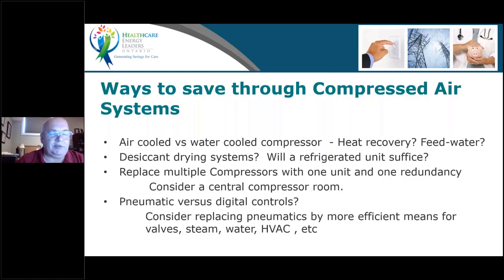Multiple compressors, so many plants have smaller multiple compressors located throughout the facility. Will one compressor do the work? Consider possibly a central compressor room. At the same time, consider a central compressor controller that will manage all the compressors simultaneously rather than having a pressure cascade where we set 3 or 4 compressors all at different pressure settings in case one fails and so on and so forth. That pressure cascade is a large waste of energy because we have to drive the last compressor to the highest pressure to compensate for a failure, whereas a central sequencer or controller has a tighter pressure band, so we can operate 3 or 4 compressors within 2 or 3 psi.